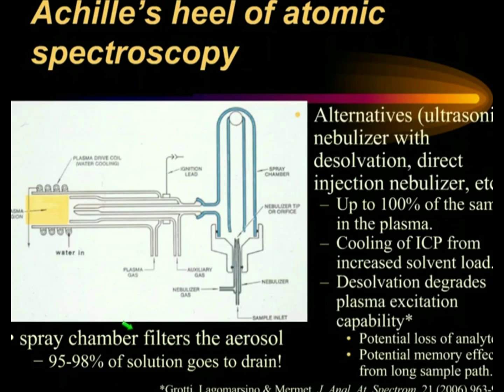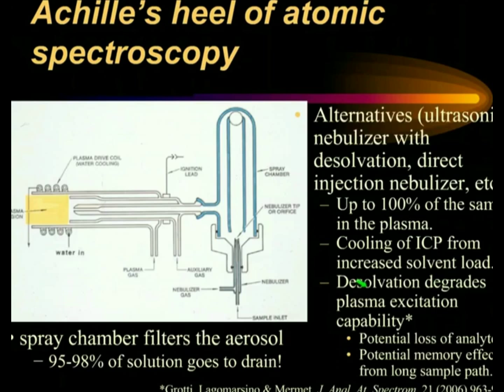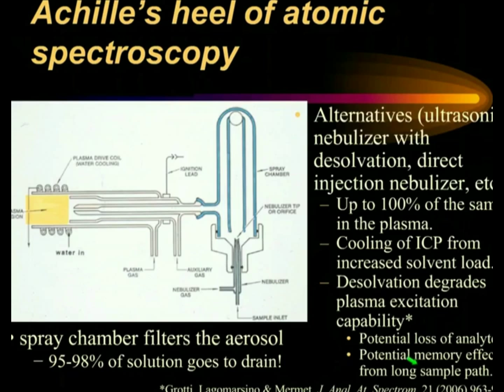There are alternatives that exist. One example is an ultrasonic nebulizer with a desolvation system. Another possibility is a direct injection nebulizer. With the latter, you have basically 100% of the sample going into the plasma, but the problem is that you also have 100% of the solvent, which cools the plasma. With an ultrasonic nebulizer and desolvation, the problem is that removal of the solvent degrades the excitation capability of the plasma. Additionally, you can lose analyte in the desolvation system, and the long sample path means samples can stick along the way, causing memory effects.